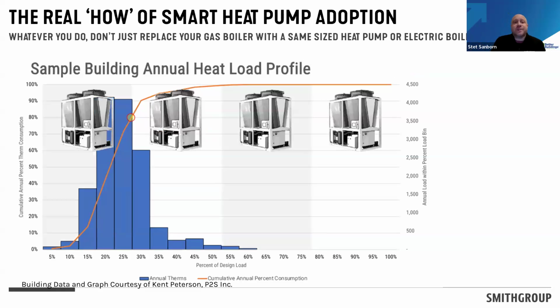When I break down those bin hours, all those hours on the far left sit at part load. One of the first strategies to reduce first cost is to focus on a hybrid system. If you already have gas boilers in place, use those to trim out the last few hours of peak load—the worst weather, super cold, polar vortex conditions everyone tells me about. Focus the heat pump on covering 80-90% of operating hours, and let the existing boilers pick up that small remaining load rather than installing very expensive heat pumps for only a few hours.